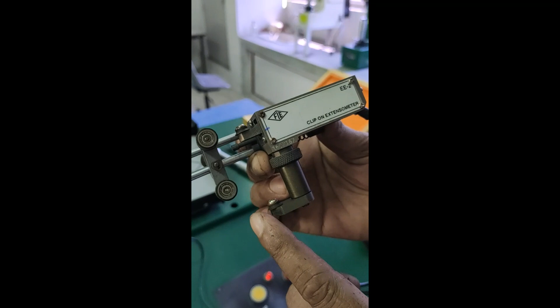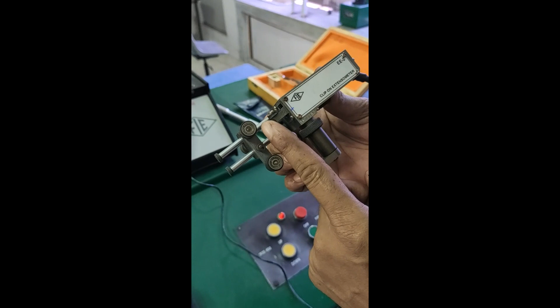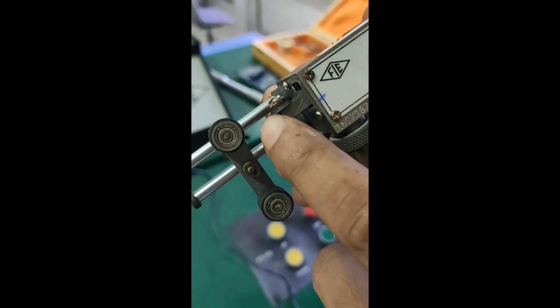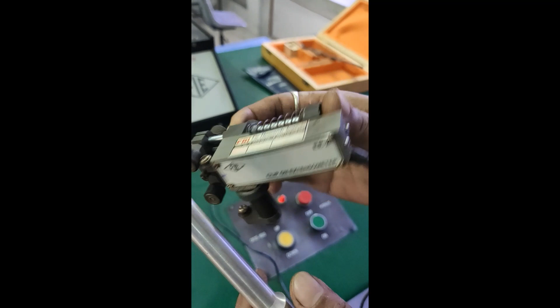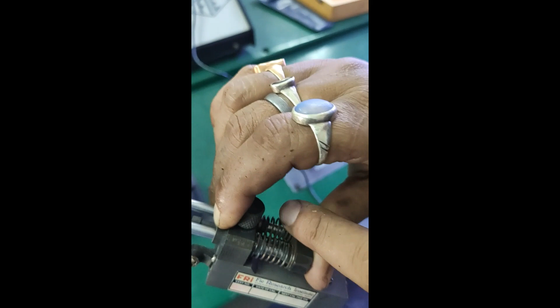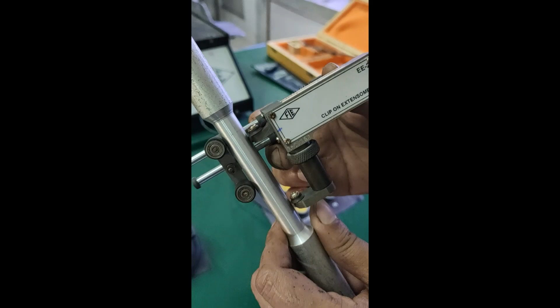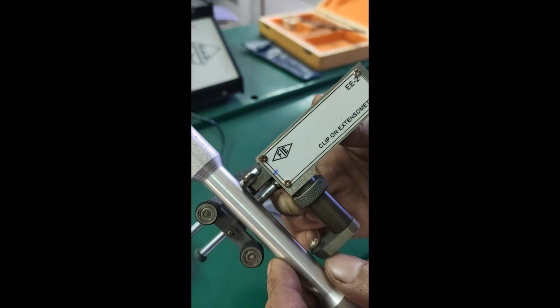This clip-on extensometer, as I told, is used for finding the strain or actual extension within the specimen. You have seen this is one knife edge, a very sharp edge, and this is another sharp edge. This will be put on the specimen like this. It is retained under spring force, so we will put it like this on the specimen during the testing. Once we fix it, what will happen? This end is fixed along with the specimen, and this end will also sit firmly on the specimen. Once the specimen elongates, this end can travel. This will be fixed, this will travel, and it can travel up to a maximum of 2 mm.